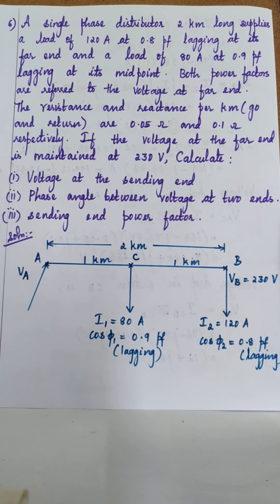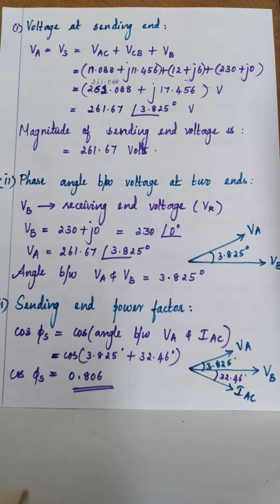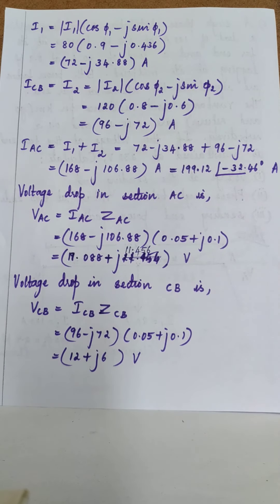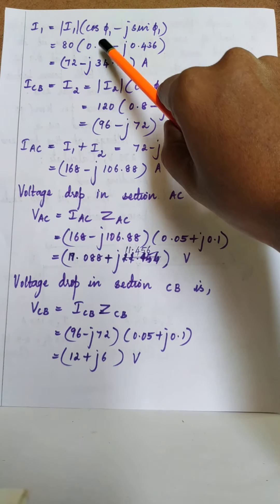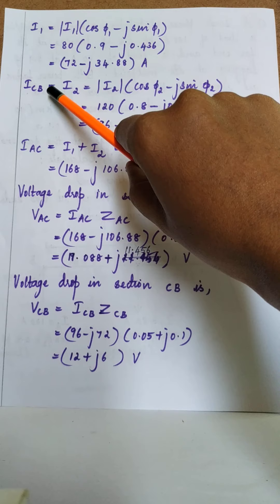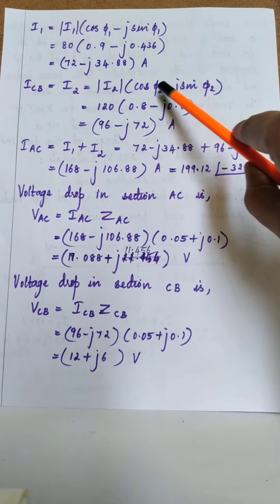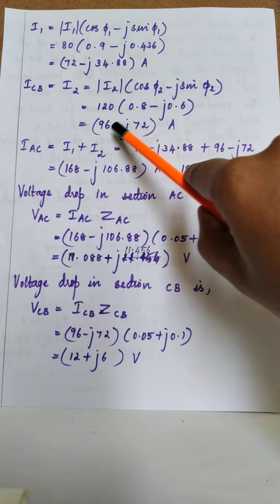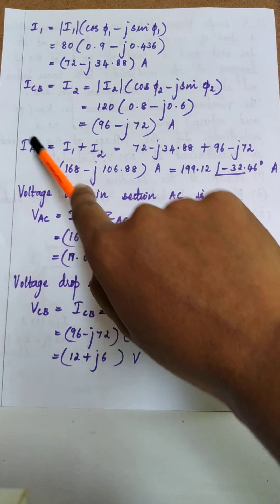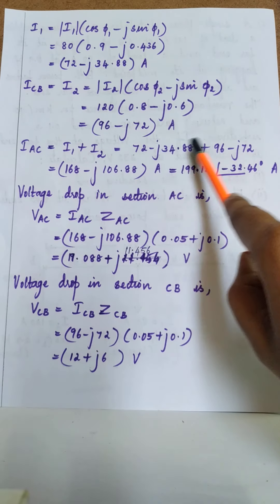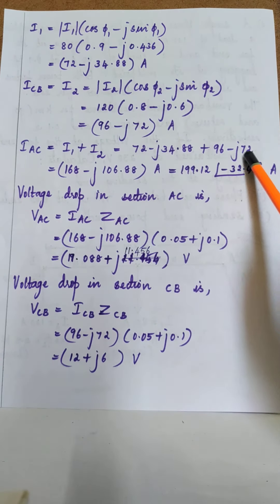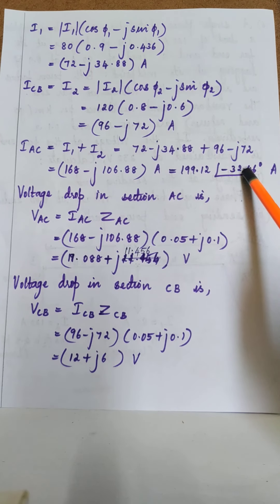Let us write I1 and I2 in complex form. I1 = |I1| (cos φ1 − j sin φ1) = 72 − j34.88 Ampere. I2, which is ICB, = |I2| (cos φ2 − j sin φ2) = 96 − j72 Ampere. Therefore the sending end current IAC = I1 + I2. We write IAC both in rectangular and polar form, since we need the angle for calculating the sending end power factor.